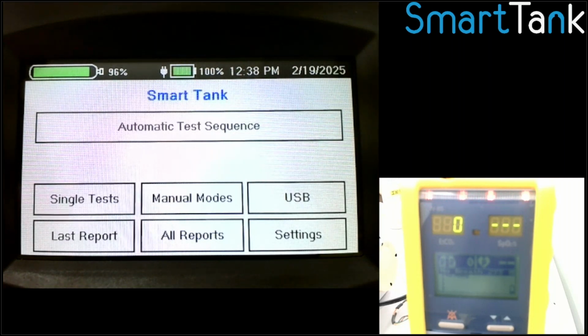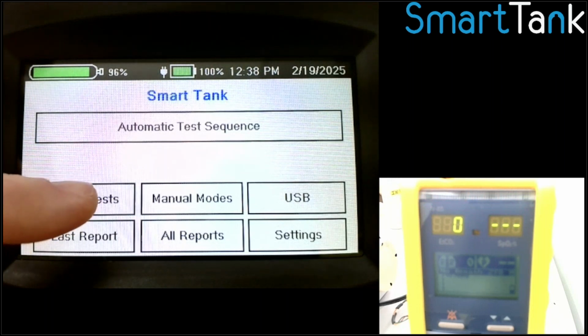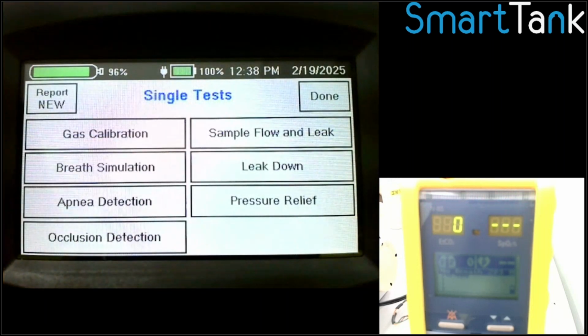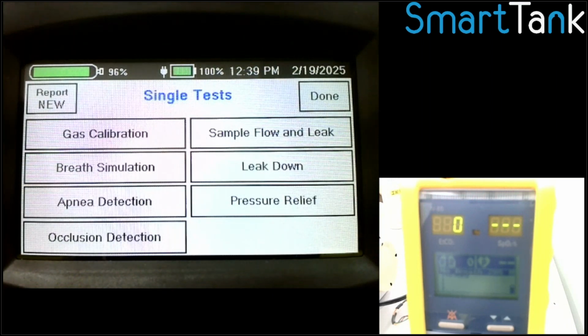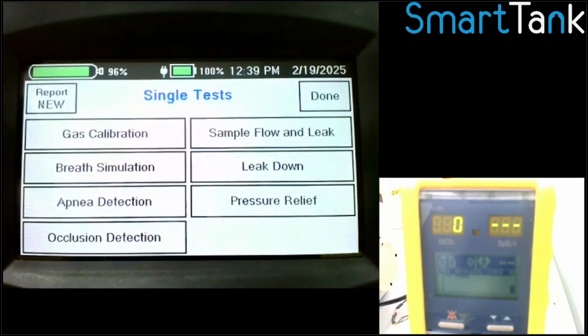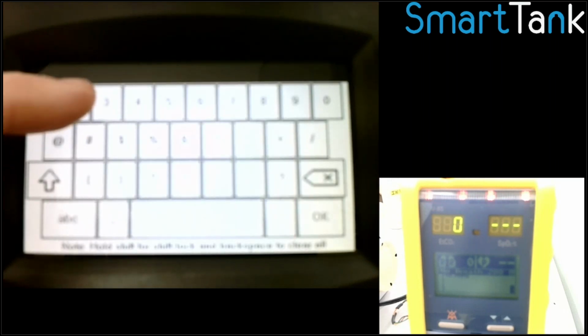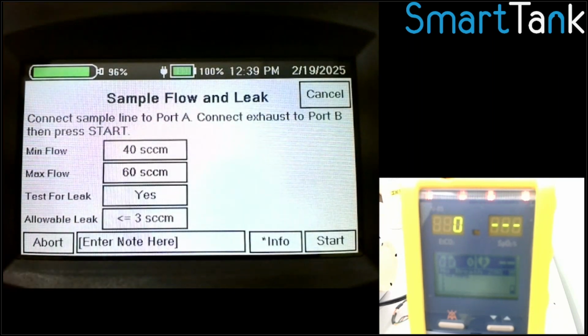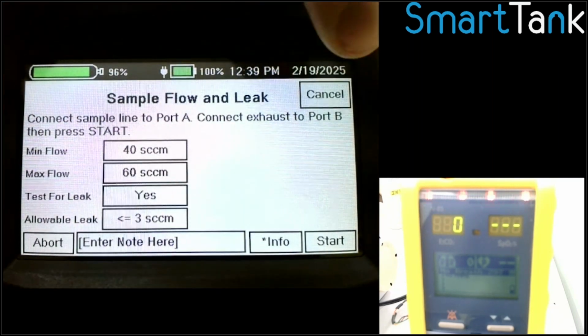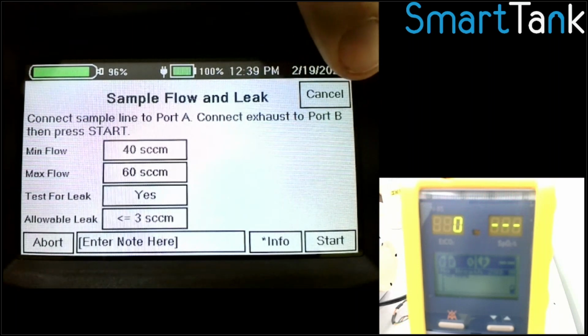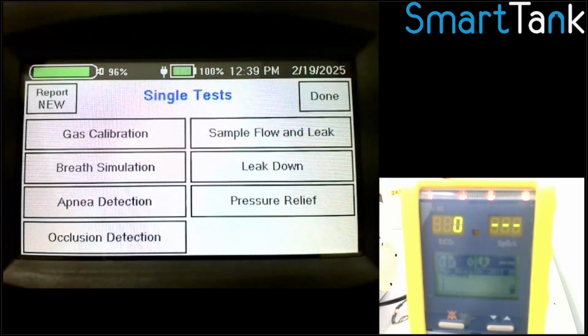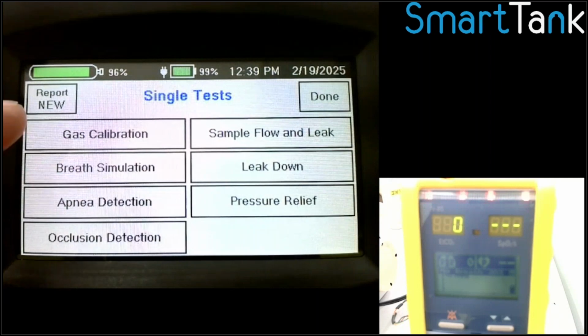There are a couple of single test modes you can repeat. So for example, if I just wanna test a machine, let's say I repaired something, I just wanna check flow and leak to make sure there's no issues. I can go in and run that flow and leak test again that we had before without running the entire sequence. I'll still get a test report. I can set the pass-fail criteria to what I want, run that test, and away we go. But also, you can do a breath simulation, just deliver calibration gas, a couple of other tests.